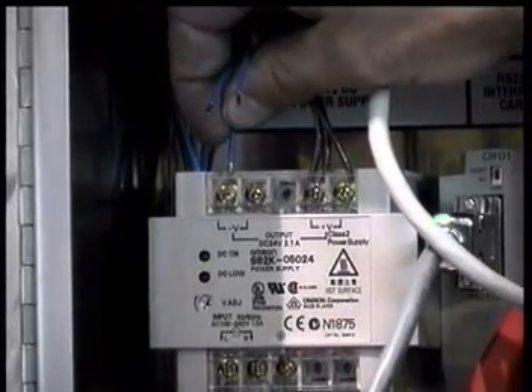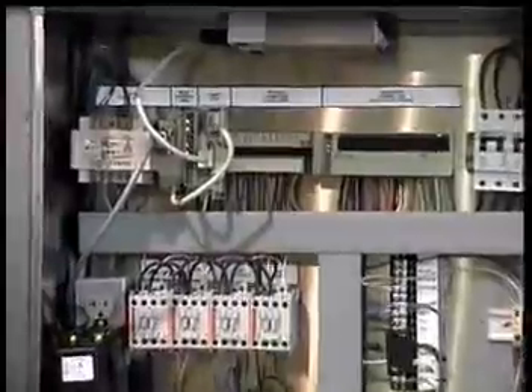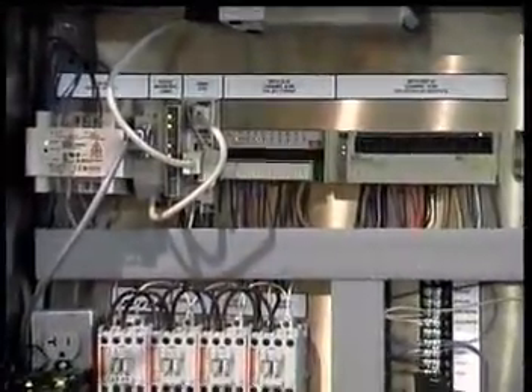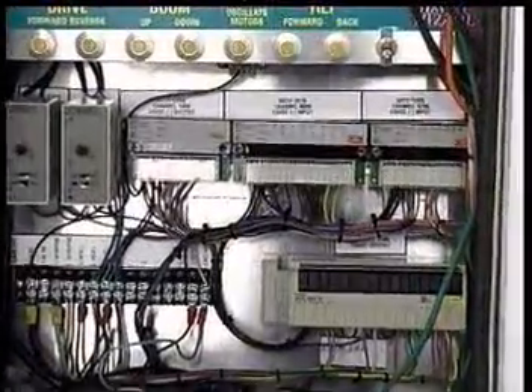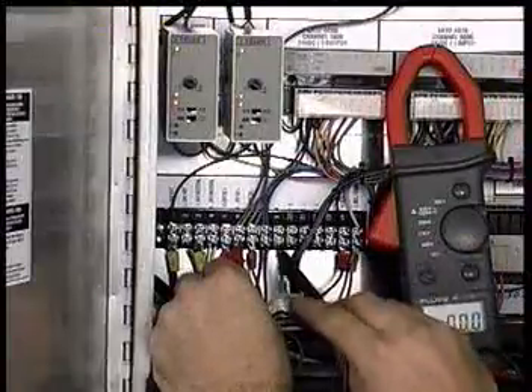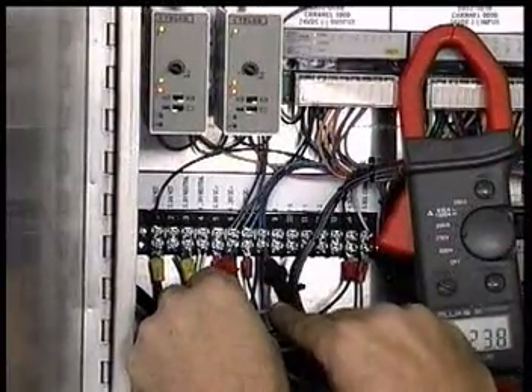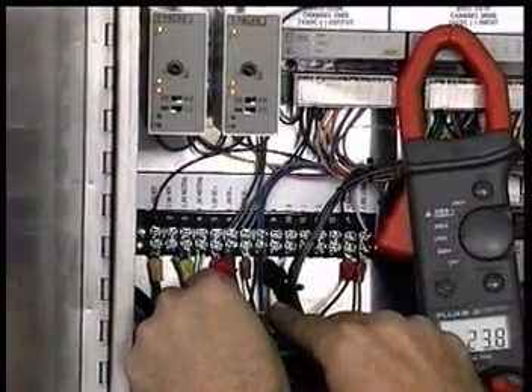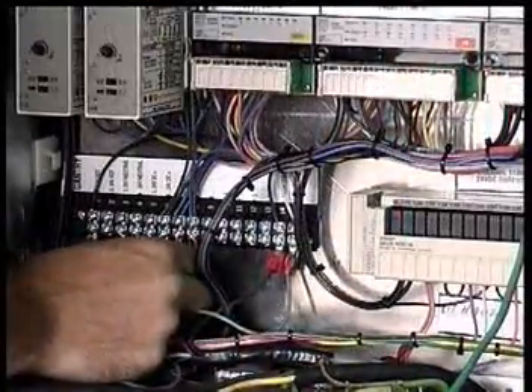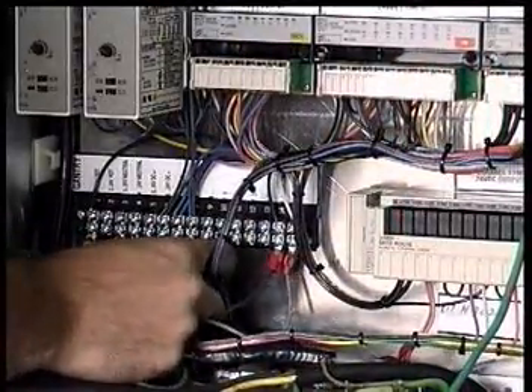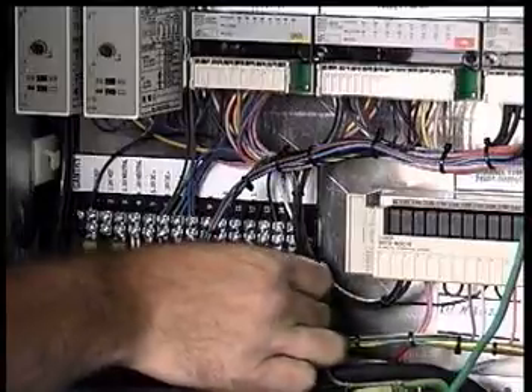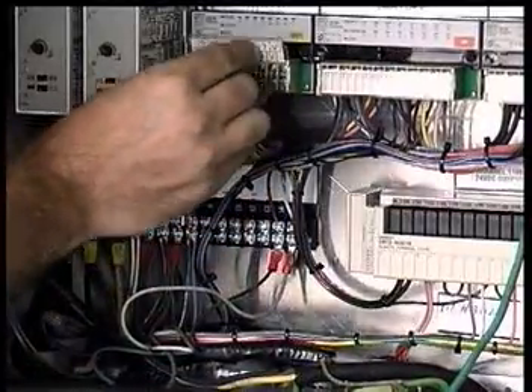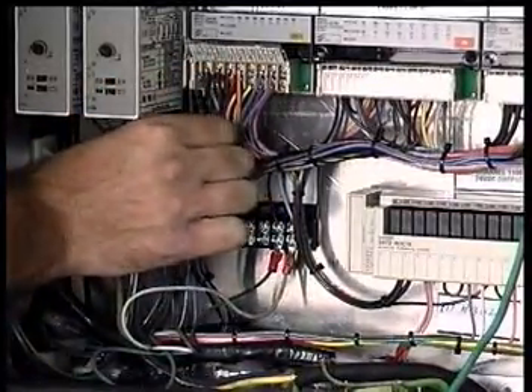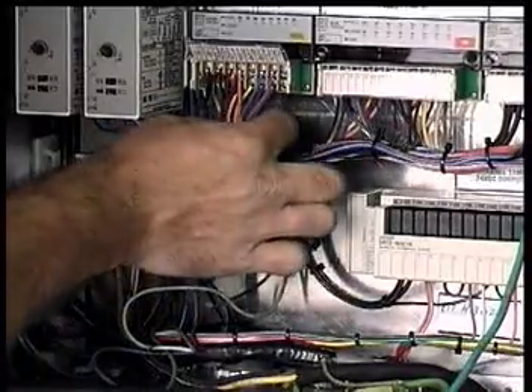If you have lights on the input-output cards on the control panel, but none at the gantry control panel, then check for 24 volt DC power between terminals 5 and 7 on the gantry terminal strip. If no power is present, make sure all cable connections in the gantry control panel are secure. If connections are secure, the problem is likely in the 4-conductor gray cable between the equipment room and the gantry.